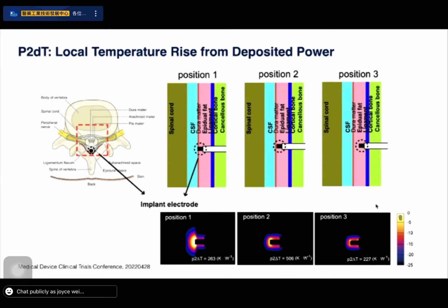So here's an example for a spinal cord stimulator. What we do to assess the power to temperature conversion factor: we look at the actual position where the implant would be placed in vivo, and we look at the local tissue environment. So the spinal cord stimulator would be near the spinal cord. And here you see 3 different positions that have to be tested, which is all part of an uncertainty and sensitivity study that needs to be done if we do simulations, to assess how much uncertainty is around what we actually simulate. So here you see 3 different setups. Once the spinal cord stimulator, a simple model, is placed directly at an interface between 2 tissues. Once there's a small offset, and in position 3 there's a larger offset.